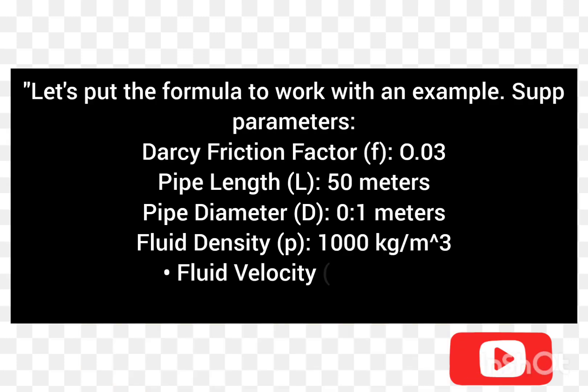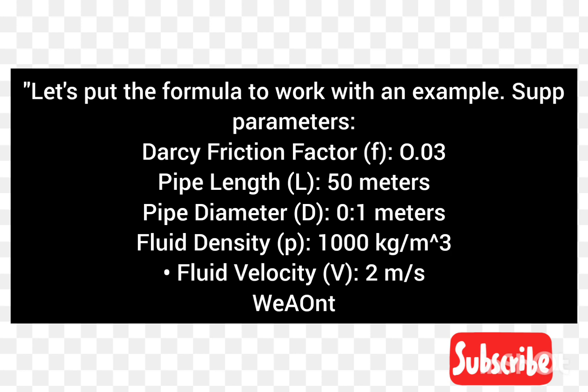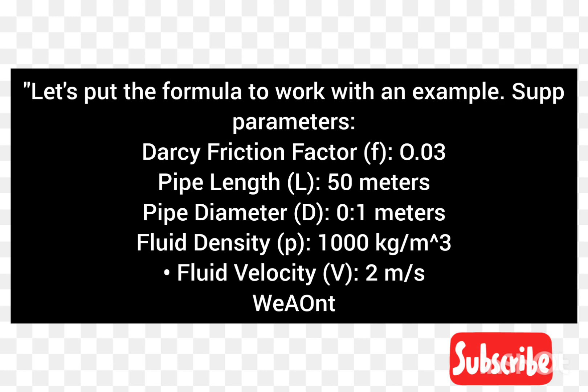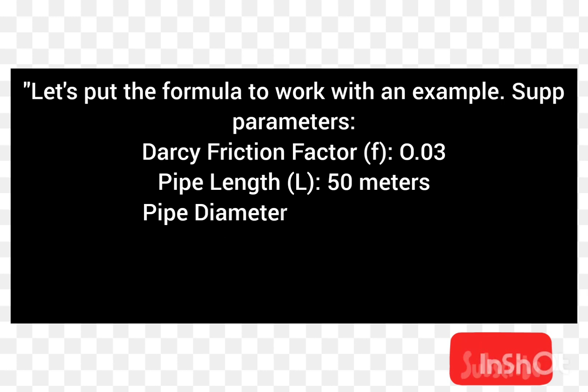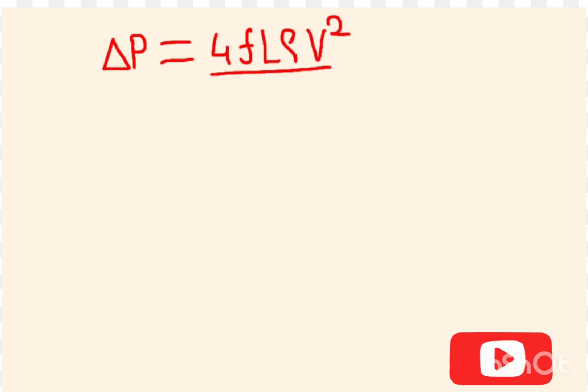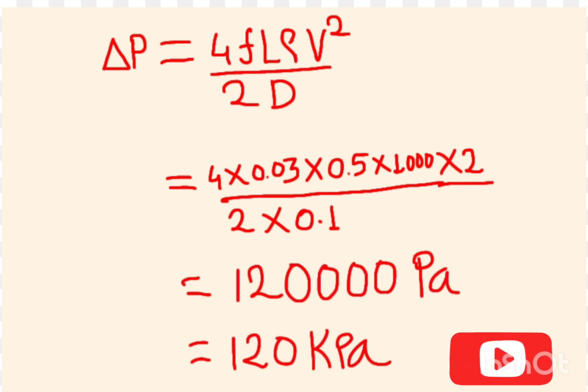Let's put the formula to work with an example. Suppose we have a pipe with the following parameters: Darcy friction factor F equals 0.03, pipe length is 50 meters, pipe diameter is 0.1 meters, fluid density is 1000 kg per cubic meter, and fluid velocity is 2 meters per second. We want to calculate the pressure drop from point A to point B. By putting these values into the Darcy equation, the final answer is 120,000 Pascals.